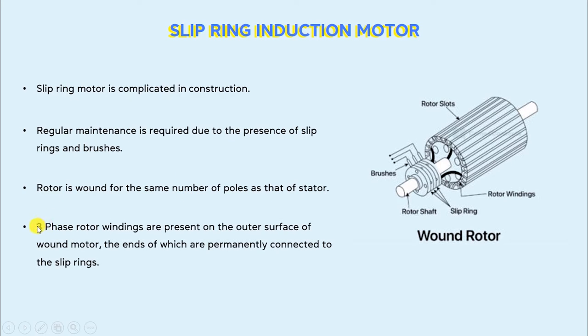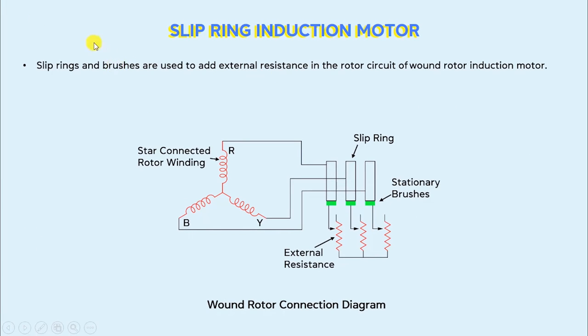Moving on to the next point: the three-phase rotor windings are present on the outer surface. These are the rotor windings, and the ends of these rotor windings are permanently connected to the slip rings. The main purpose of slip rings and brushes in a slip ring induction motor is to add external resistance in the rotor circuit of a wound rotor induction motor. In the diagram, this is the external resistance in the rotor circuit, connected with the slip rings and stationary brushes.